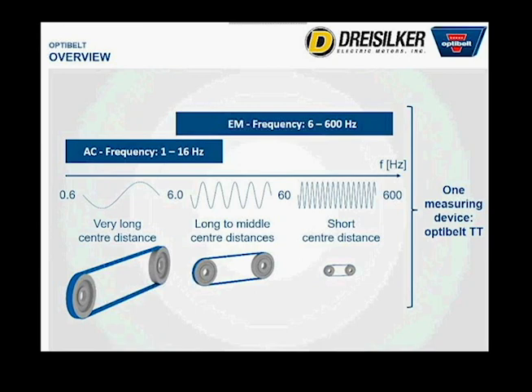It shows the various frequencies it can measure. The accelerometer is for very large belts, 500 to 600 horsepower drives with massive belts that can be almost a foot wide. Then as you go up in frequency, you have small belts like the ones on mushroom fans.